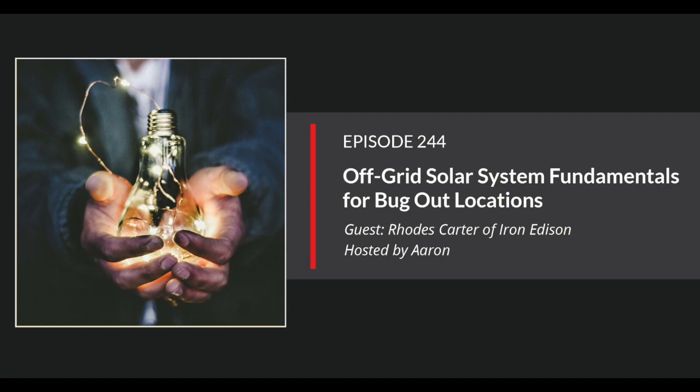Okay. So we've broken this all down and gone through the three major categories of load, storage, and generation. How do we pull it all together and start, in layman's terms, designing a system, at least in our heads, and playing around with it? The first step to properly design a solar system, as we mentioned earlier, is to know what your electrical loads are: both the amount of energy you're going to use per day in kilowatt hours, as well as how much power you need if everything's turned on all at once. The amount of energy in kilowatt hours will help us decide the size of battery and how much storage we need. The amount of power if everything's turned on will dictate how big the inverter is. The inverter is the component that converts the DC energy stored in the battery to the 120 volts AC that powers your home.